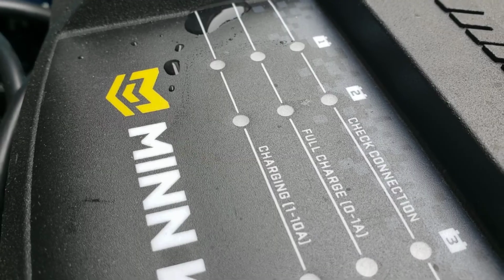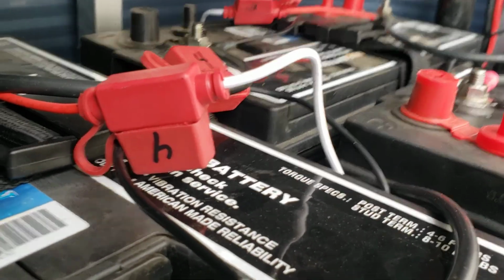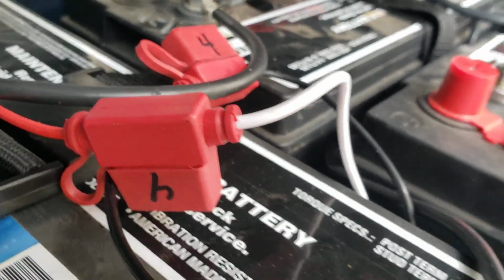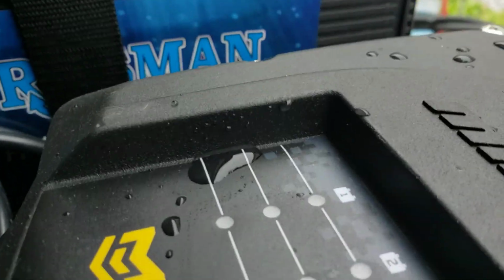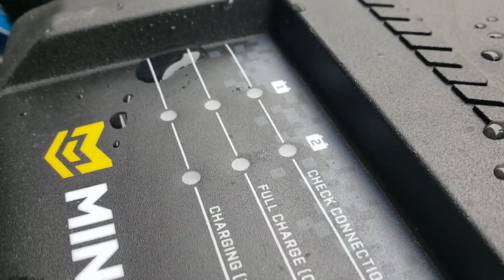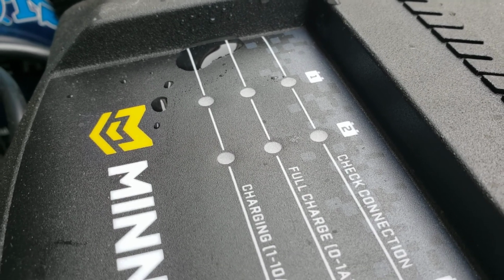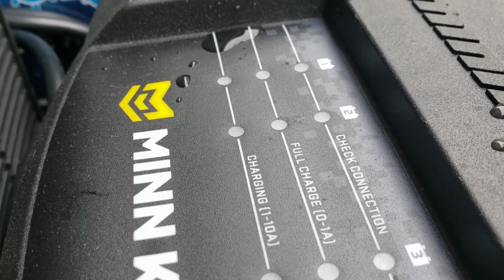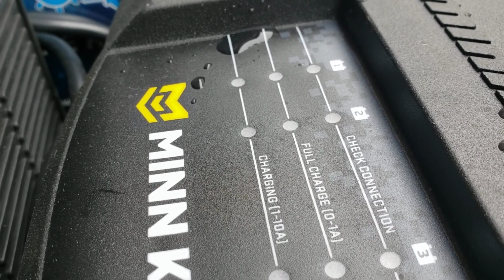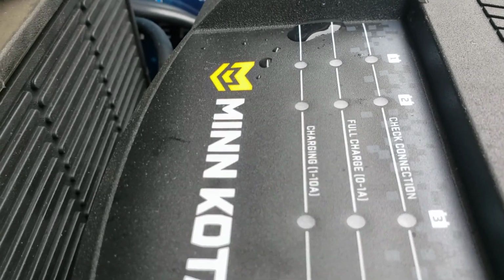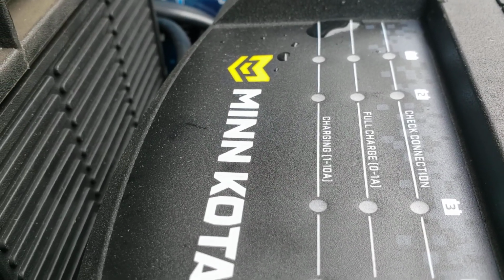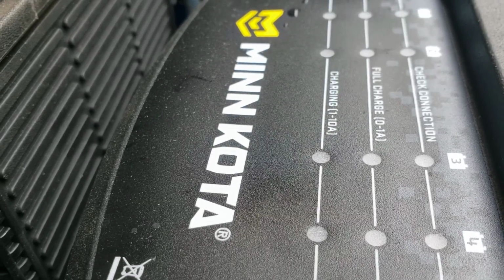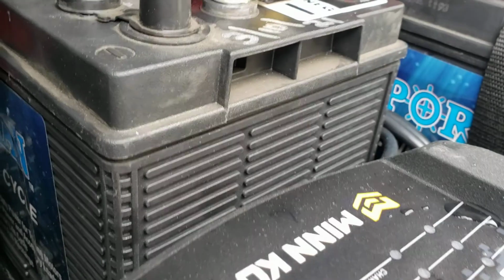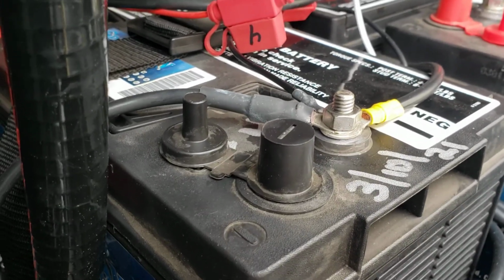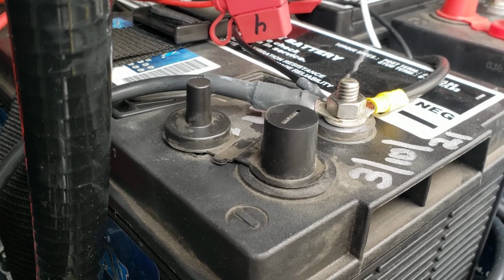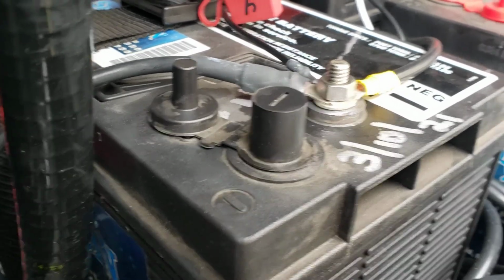That would mean that potentially one of these fuses could be blown, and there's a fuse on both the positive and negative lead on each battery. So if one of those fuses is blown, you would get a check connection light, or in the case of one of the batteries being below about 8 volts, the check connection light would be on without a blown fuse. That means the battery voltage is lower than the threshold that the charger will charge. If that happens, you would need to take a separate charger and charge that one battery individually to bring it above the bottom threshold, and then the charger should take back over and do its thing.